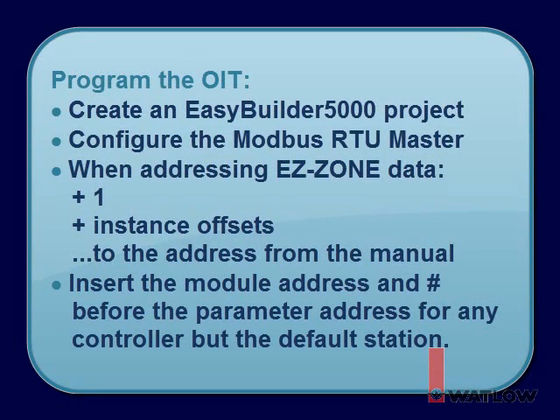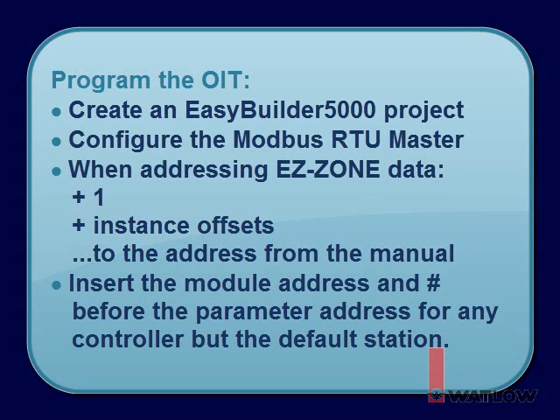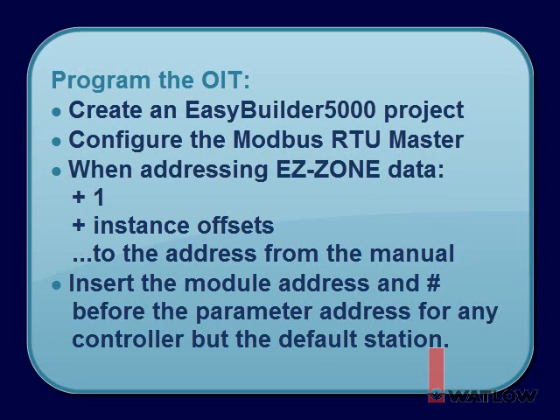Switch the controllers to Modbus protocol, create a new EasyBuilder 5000 project, configure the Modbus RTU device that appears by default with the correct COM port and Modbus communications settings. When addressing data in EZ-ZONE devices, add 1 plus any instance offsets to the Modbus address found in the EZ-ZONE users manual, and remember, insert the RM module address and a pound sign or hash mark before the parameter address to get data from a controller other than the default.